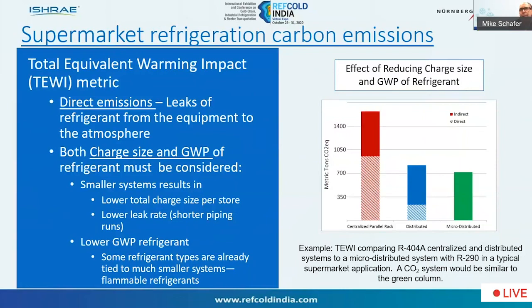In this example, R290, given the charge size, is going to have a much smaller refrigerant charge leak rate. And this illustration on the right would be the effects of reducing the charge size in GWP, comparing the centralized parallel rack compared to the distributed system and a microdistributed system. So clearly the microdistributed with a natural refrigerant only has the indirect contribution. And then CO2 would be very similar to what was shown here in green for the microdistributed.